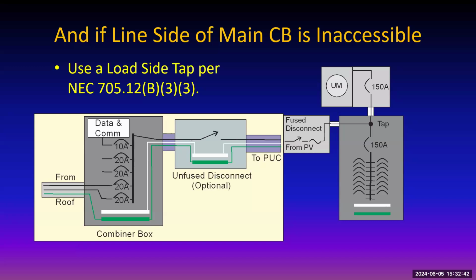And so what's the deal? Why is this? Well, for one thing, the 150 amp on the main distribution panel says that no more than 150 amps can go there, no matter where it comes from, utility or otherwise. So that says the utility is there, but you just have two options for feeding those loads. Sometimes both of them will be working. You've got 150 and the utility is there and the PV is there. And so the first choice is from the PV and whatever's left over comes from the utility.